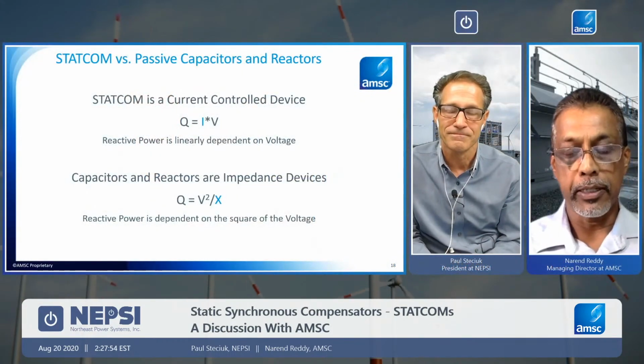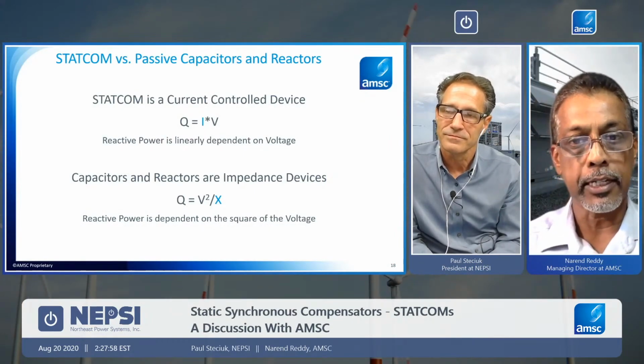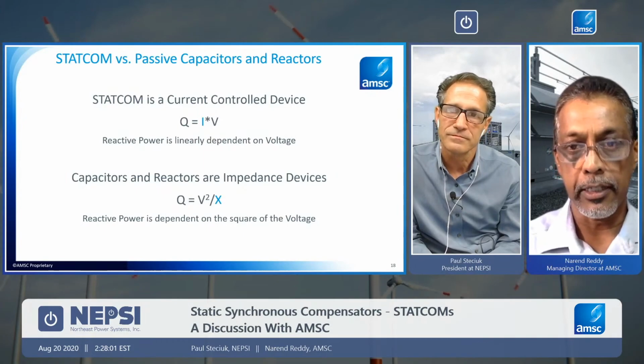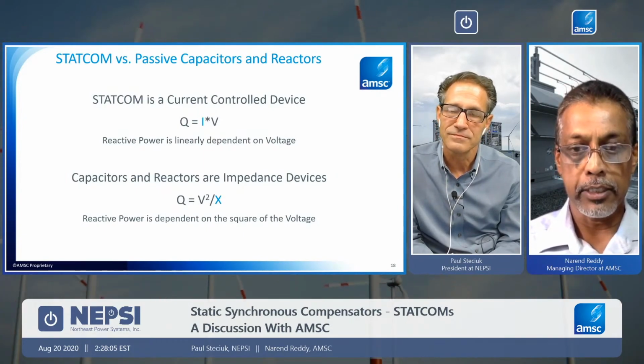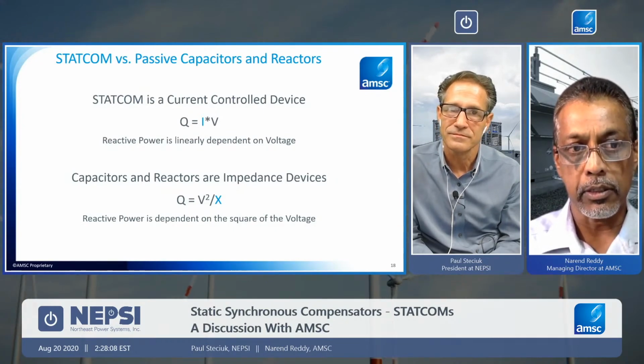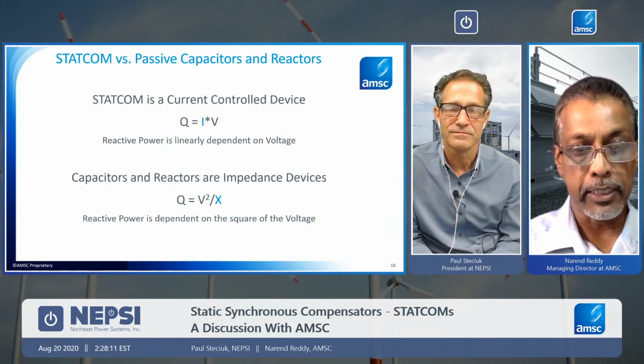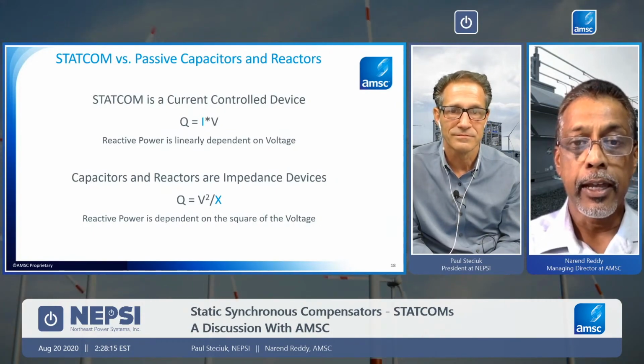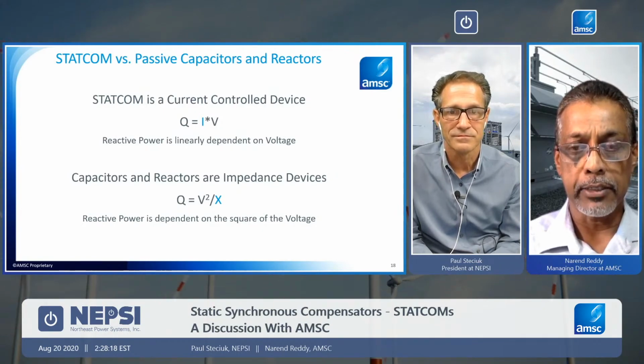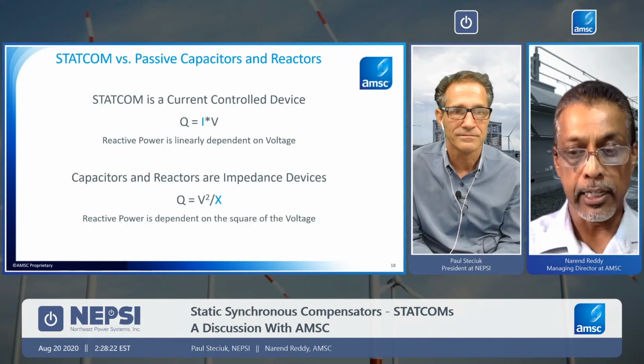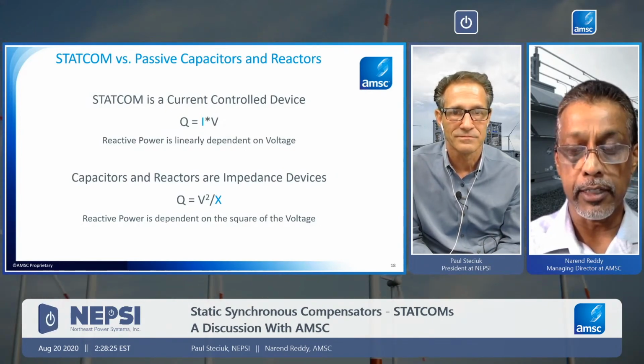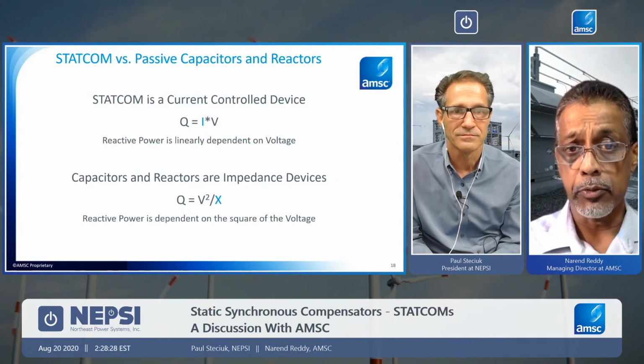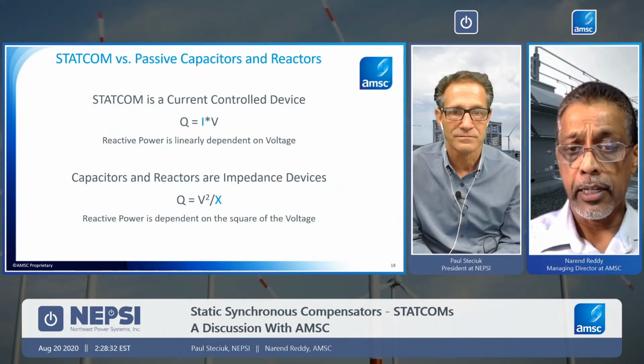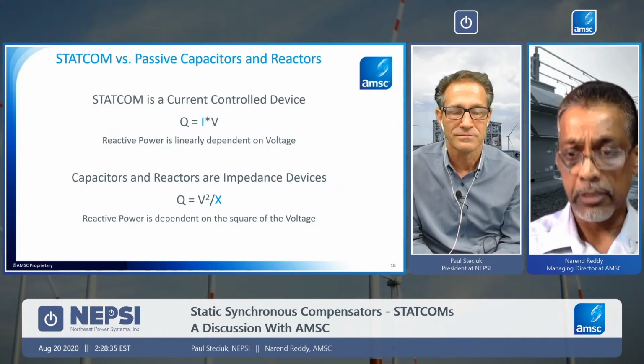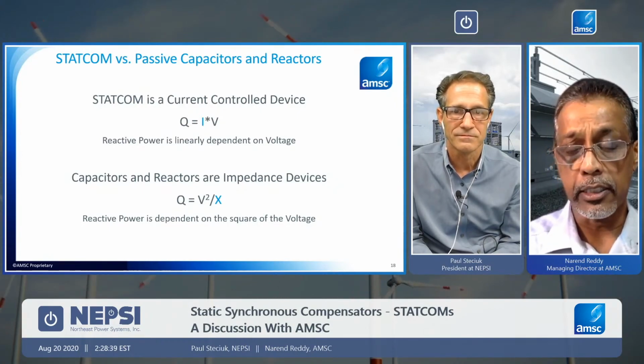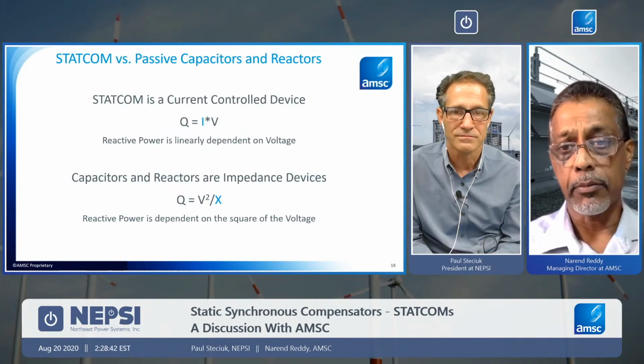So you bring up a good point, and as I mentioned earlier, a STATCOM is a current control device, meaning that the output of the device is a certain amount of current that is controlled, with a certain magnitude as well as a certain phase angle, whether leading or lagging. So the vars, or the reactive power that it is injecting into the grid, are directly proportional to voltage. So Q equals I times V. As opposed to capacitors and reactors, which are either switched in or out on their own, or utilized as part of other devices such as a static var compensator.